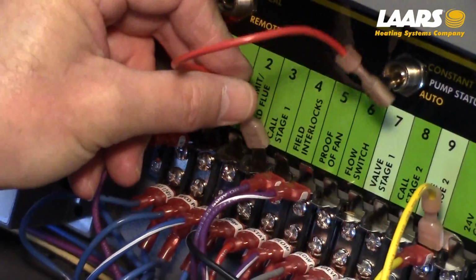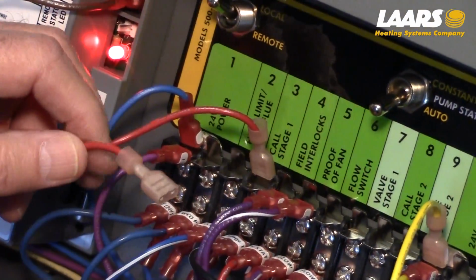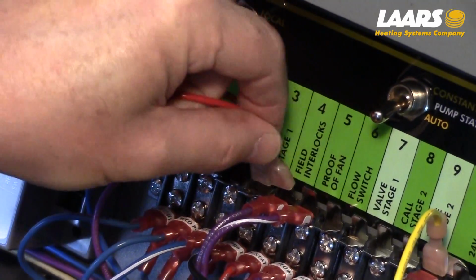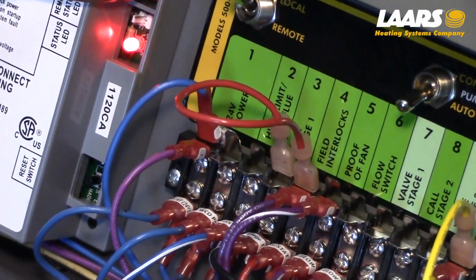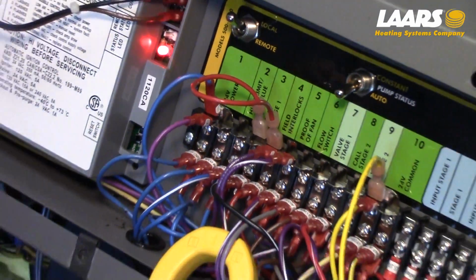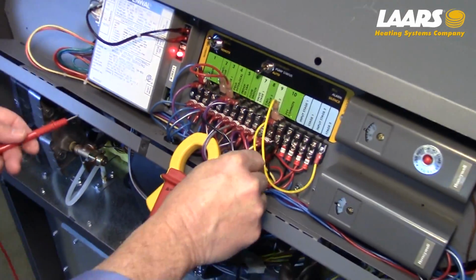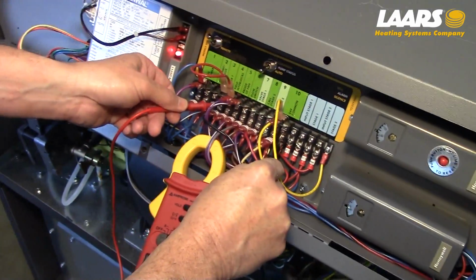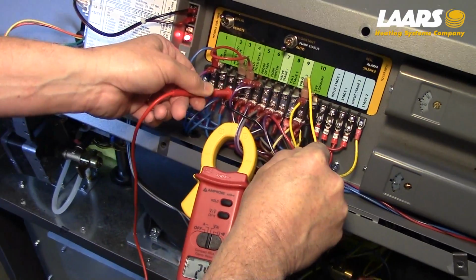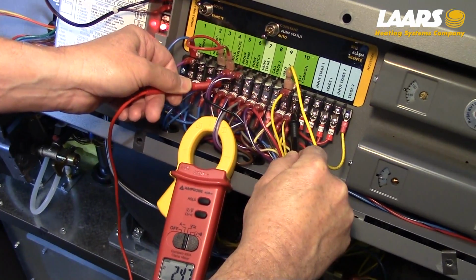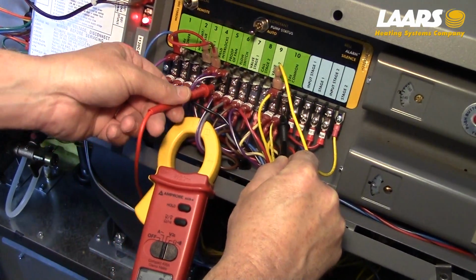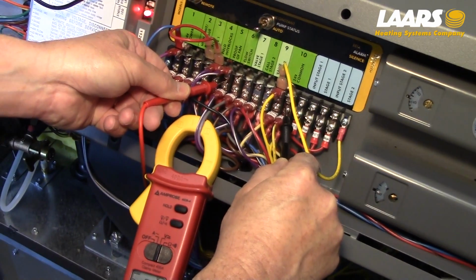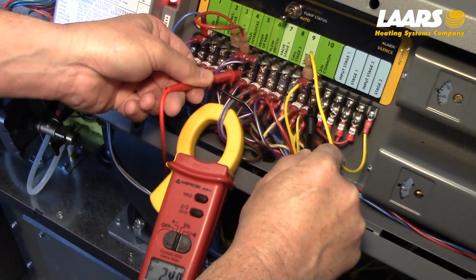Okay? I'm going to put a jumper on my terminal 3 and terminal 4 for call for heat. Okay? With the meter, I can walk through it. I have it at 24. I have it here at terminal 3. I now have it here at terminal 4. I then go to my proof of fan. Alright, I also have it in my proof of fan.